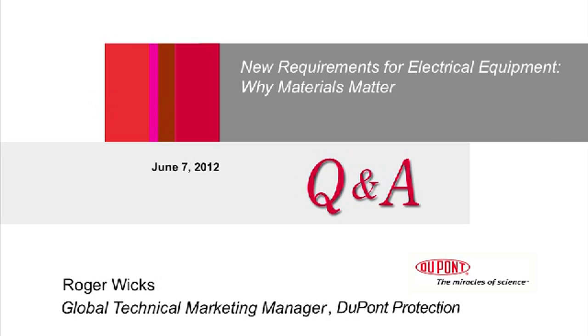Question has come in. What is the shortest aging time that should be considered in order to achieve the equivalent of one IEEE life? Gee, that's an interesting question. Again, a lot of it depends on the requirement that you're doing the aging for. Most of the IEEE test protocols were established based on 20,000 hour life. And in such an evaluation, we like the shortest time to be around 100 hours and the longest time to be around 5,000 hours.